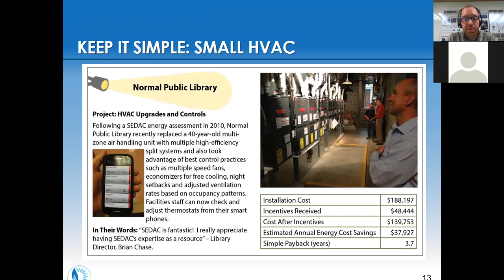This system was in desperate need of maintenance and repair, with heating and cooling happening simultaneously. What they ended up doing was an elegant solution of 10 basically residential furnaces and air conditioners. There's a lineup of all the different units with PVC pipes - these are condensing units, above 90% efficient. They were able to implement this.